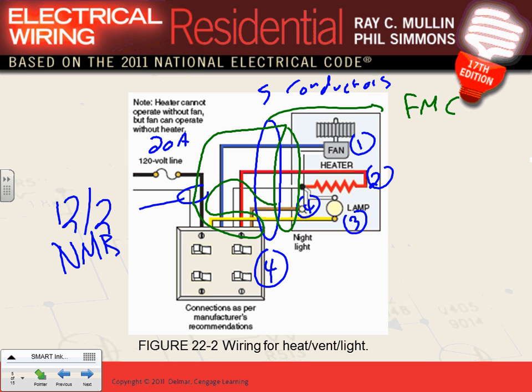So I need a controller. First of all, where is the controller for the equipment? Here. Where are the disconnects? These switches are your disconnect. The exhaust fan, where's the disconnect for your exhaust fan? The same switch that turns it on and off is its disconnect. The code allows you to use the snap switch as your disconnect. Any comments, any questions, guys, about that?